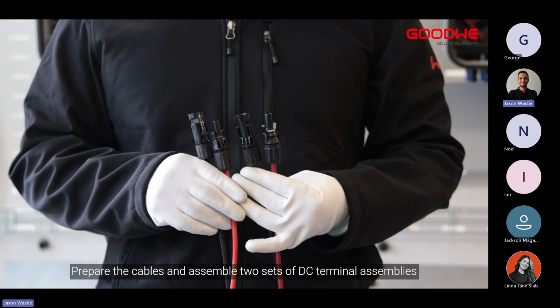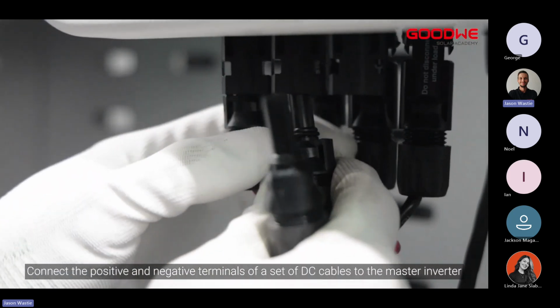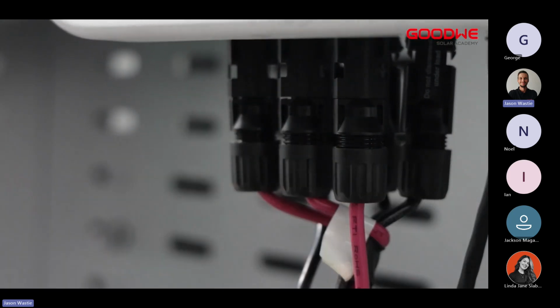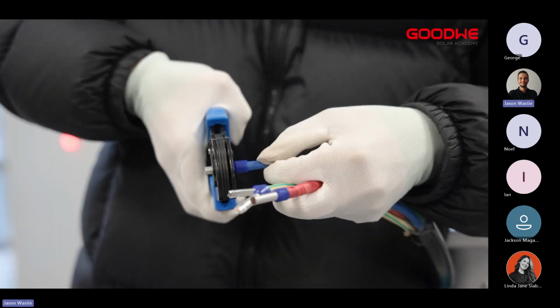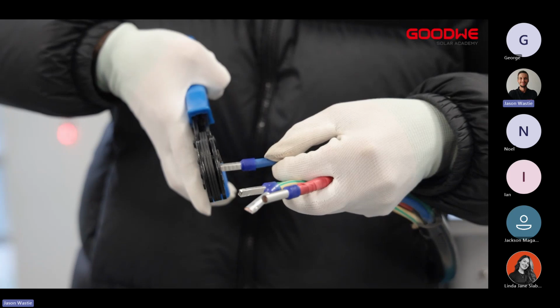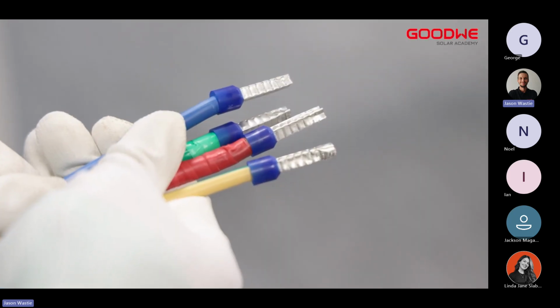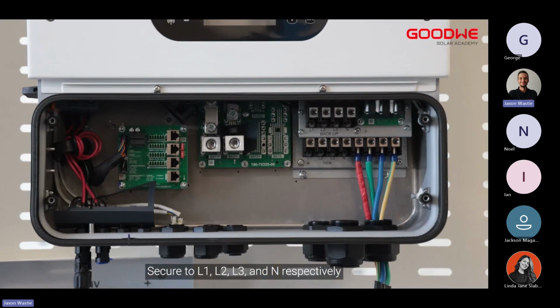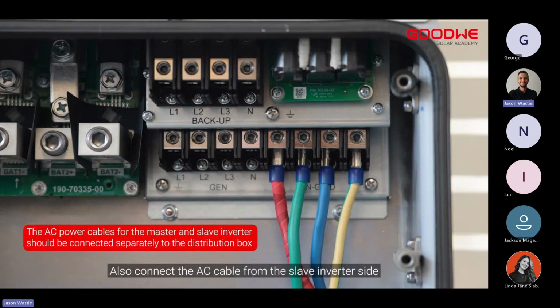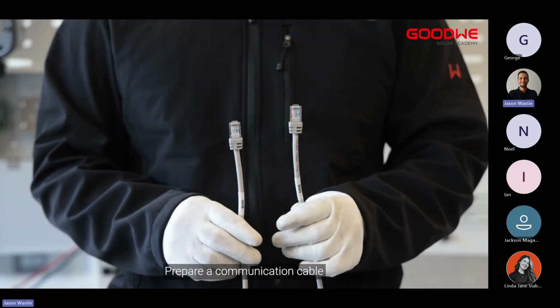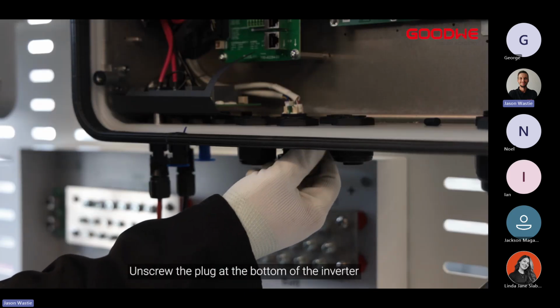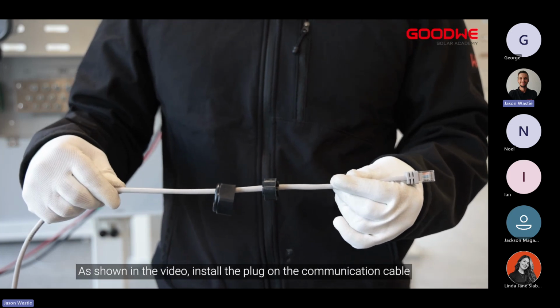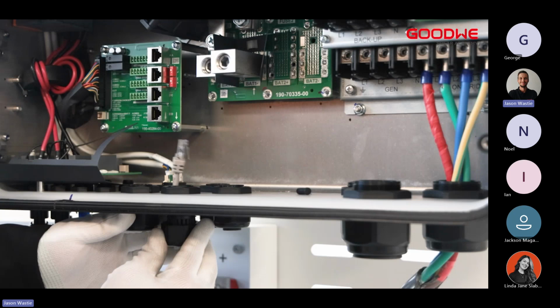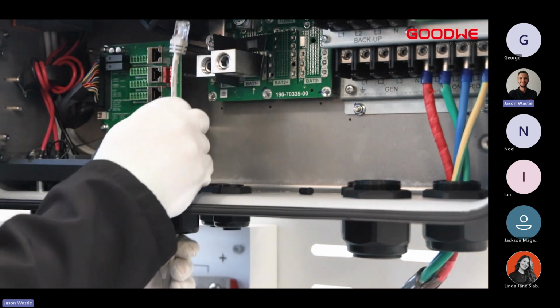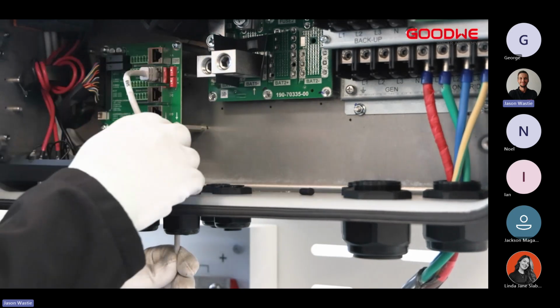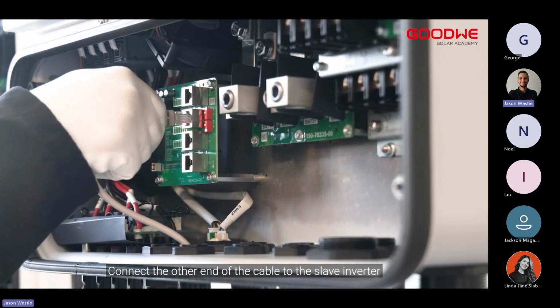Prepare the cables and assemble two sets of DC terminal assemblies. Connect the positive and negative terminals of a set of DC cables to the master inverter. Next, make the AC power cable. Secure to L1, L2, L3, and N respectively. Also connect the AC cable from the slave inverter side. Parallel operation of the inverter. Prepare a communication cable. Unscrew the plug at the bottom of the inverter. As shown in the video, install the plug on the communication cable. Finally, connect the cables to the inverter. Connect the other end of the cable to the slave inverter.